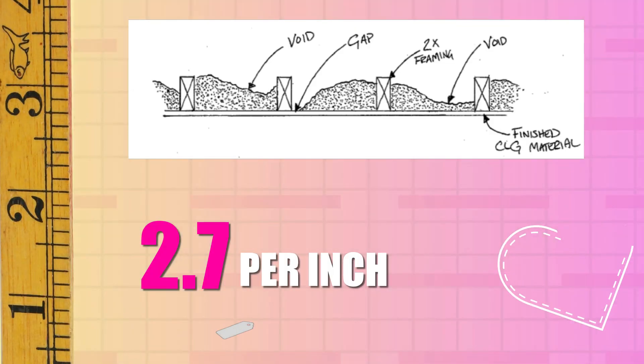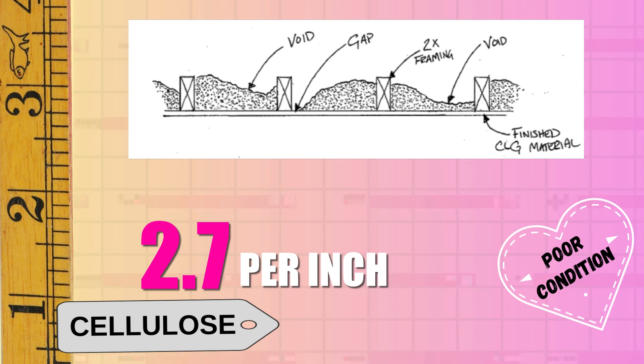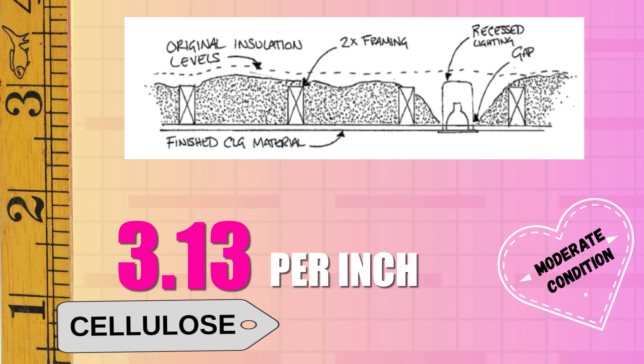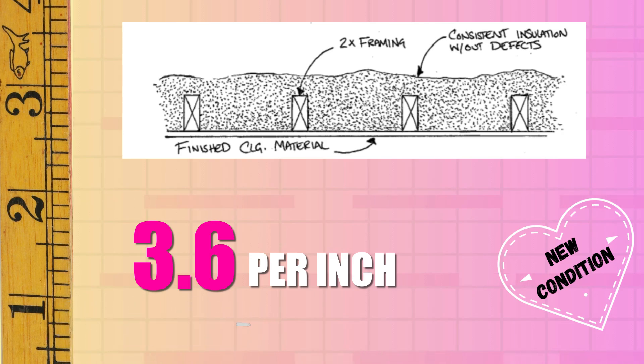If you find loose fill cellulose insulation in your attic and it is in poor condition, you can assign it an R-value of 2.7 per inch. Moderate condition is 3.13 R-value per inch. New cellulose is calculated at 3.6 R-value per inch.